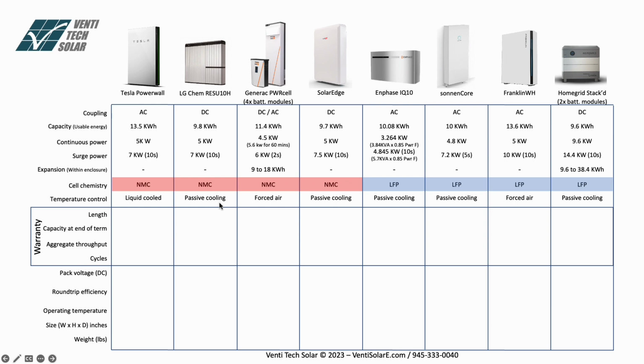Passive cooling is basically letting heat dissipate based on the air surrounding the environment. Generac in here is using forced air, so it has fans in the top or the bottom to circulate room air through the enclosure to cool the cells and carry away that heat. Again, NMC with passive cooling, I think it's a recipe for disaster. In the LFP, active cooling is not necessary, so no fans or water cooling or glycol forced cooling is necessary, so this is perfectly acceptable.